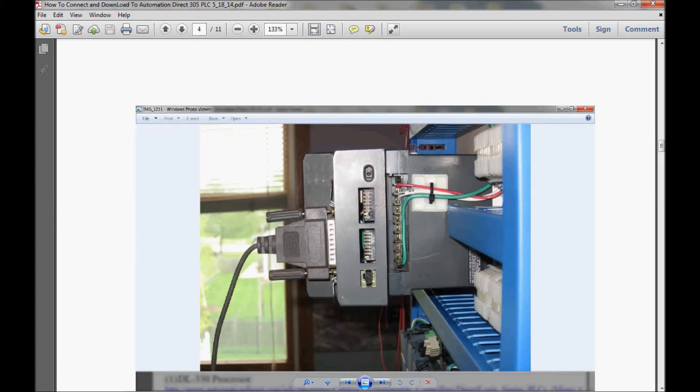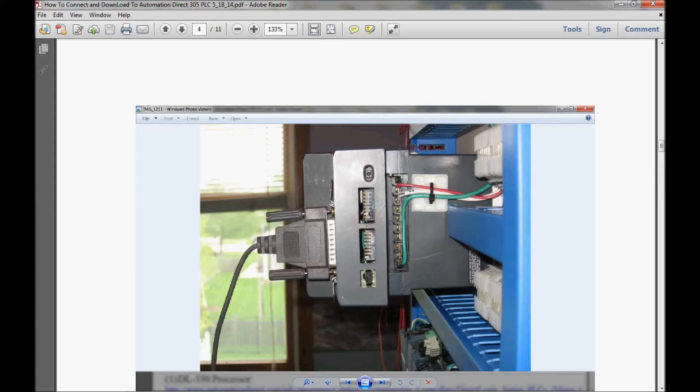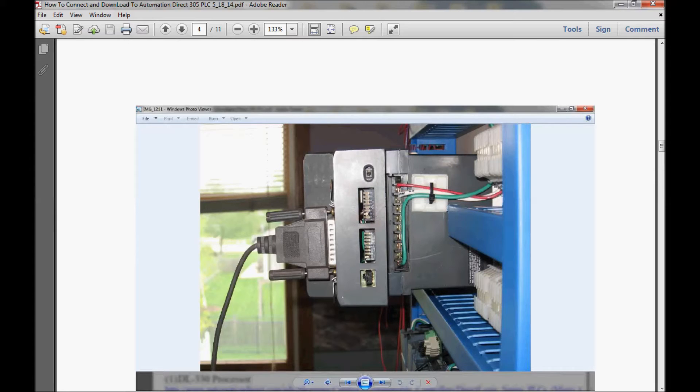On block 1, that sets the communications protocol. The only DIP switch that I have selected there is DIP switch number 2, which starts from the bottom. Number 1 is at the bottom, then number 2 all the way up through to number 8 at the top. Number 2 is pushed to the left. All the rest are pushed to the right.